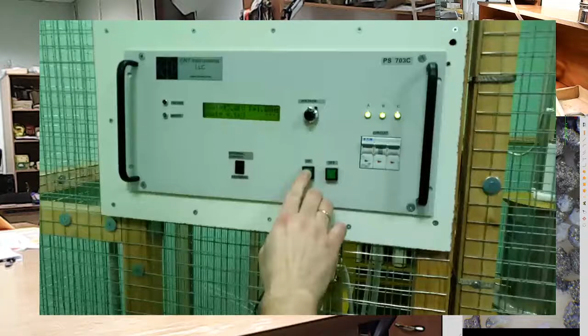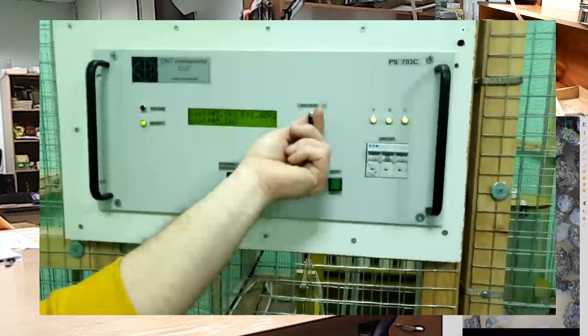We are now at 43 kilovolts. We remember that it starts discharging around 50 kV. There will be sporadic sparks from the beginning, but then it will be steady. We're increasing the voltage slowly, 0.1 kilovolt a second, to make sure the discharge happens at a certain time, and once it's started, you just continue processing the sample, and we have it all processed eventually. Okay, we've had several discharges, and now it all stops.